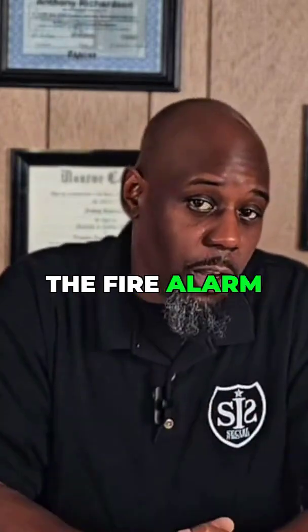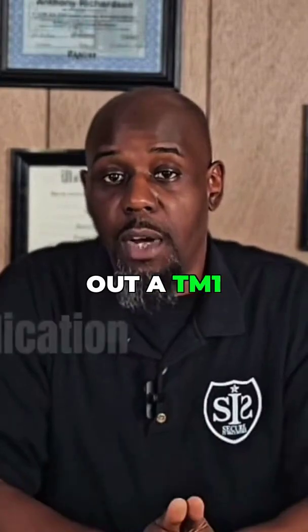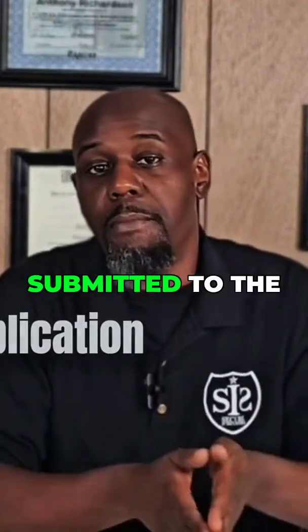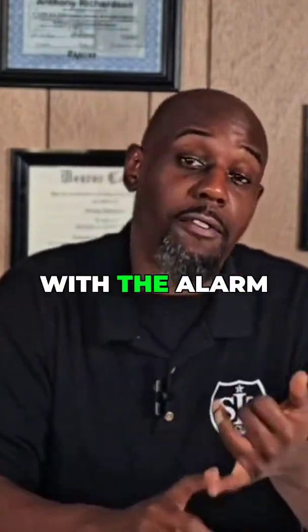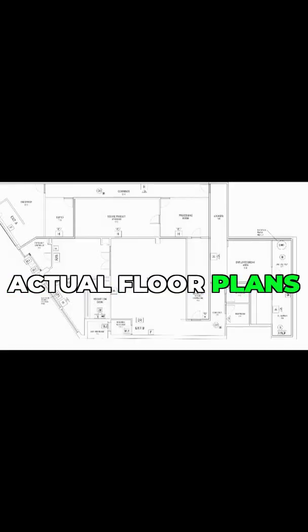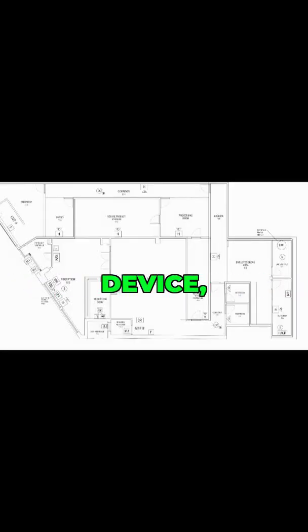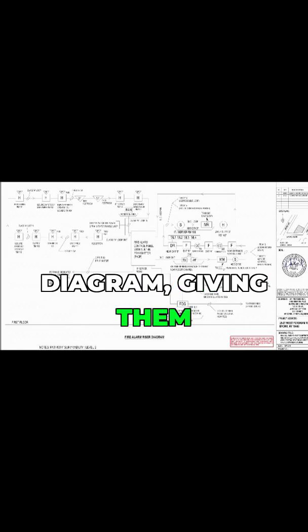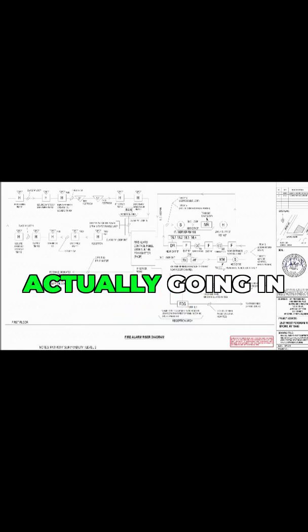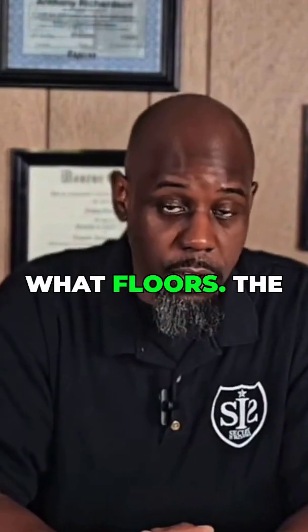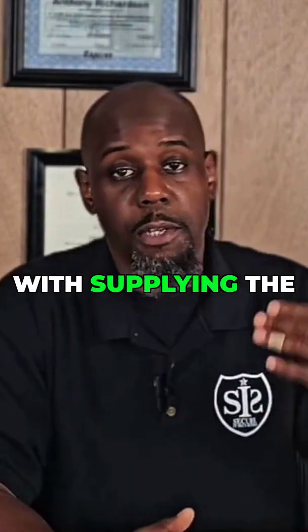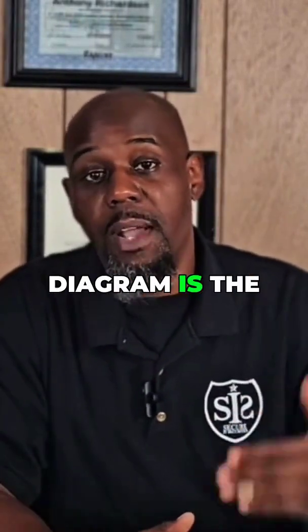After we design a fire alarm system, we have to then fill out a TM1 application. This application is submitted to the fire department along with the fire alarm design, which is actual floor plans of where we're going to put each and every device, fire alarm riser diagram, giving them a one-line diagram of what's actually going in the building and what floors.